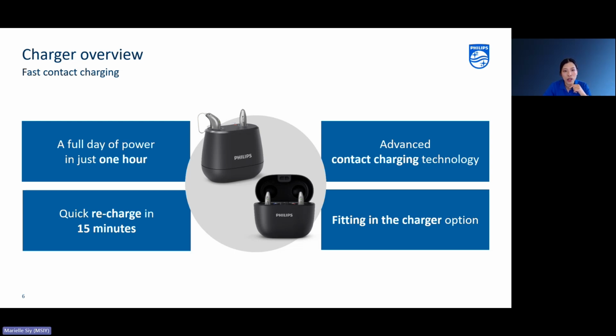And then contact charging also brings a clinical benefit that many hearing care professionals really appreciate, which is that you can program the hearing aids while they are charging. So if your client arrives in your clinic with a low battery and you need to do a firmware update, you can do the firmware update while it is charging. That's really efficient. It doesn't have to be in the charger when you're connecting it to HearSuite, but it's possible.